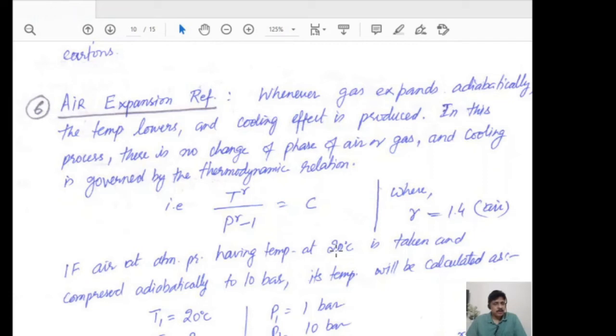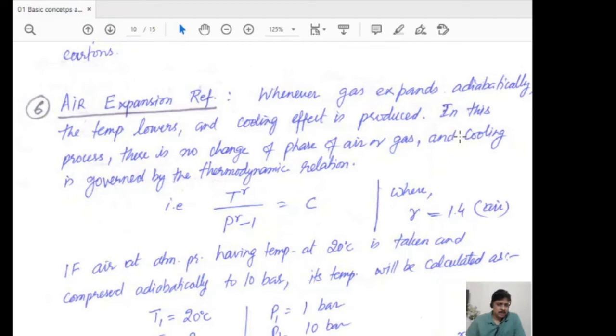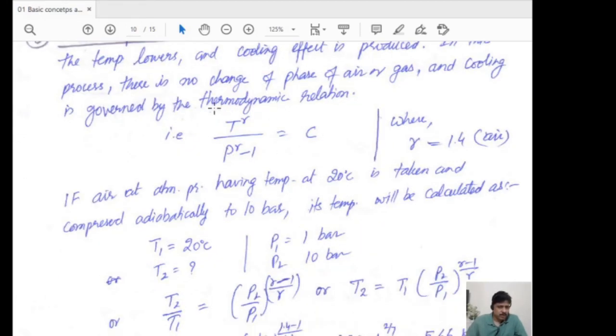The air expansion refrigeration system, also known as the air refrigeration system, is a process in which we expand the air. First, we compress the air to a very high pressure and then expand it. Whenever a gas expands adiabatically, the temperature lowers and a cooling effect is produced. When we pass gas through a small, narrow passage, it expands and instantly absorbs heat from the surroundings, producing a cooling effect. There is no change in phase of the air. The governing equation is T raised to gamma divided by P to the power of gamma minus 1 equals constant, where gamma equals 1.4.